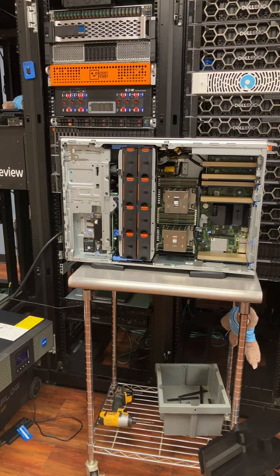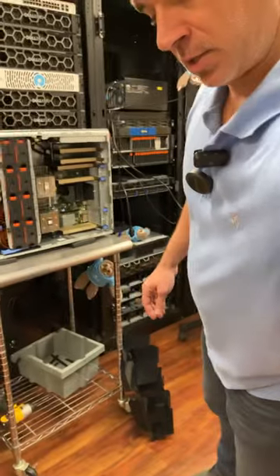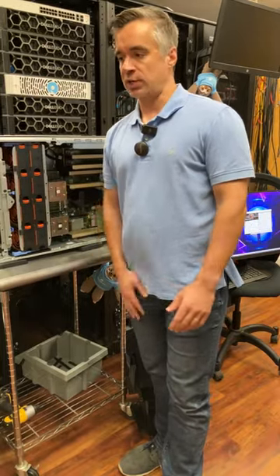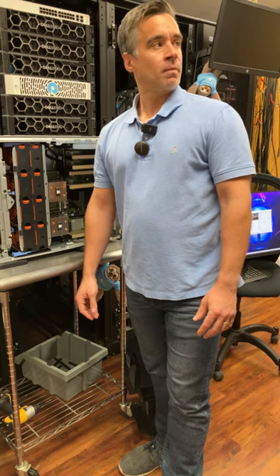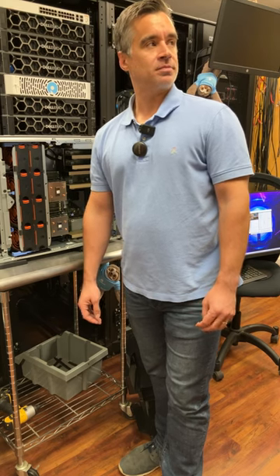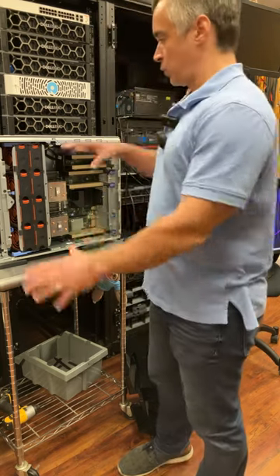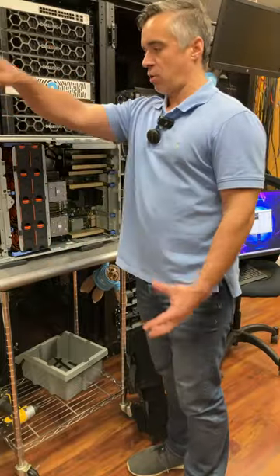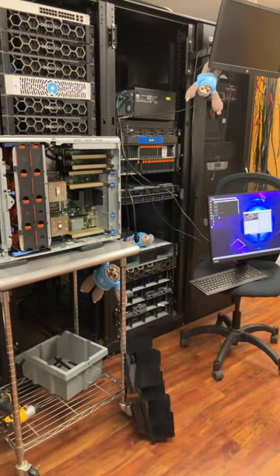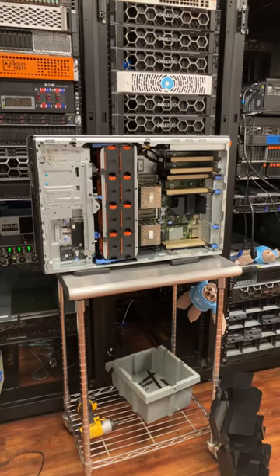I don't know if you were talking about it, but we spent a bunch of time in Dell's labs in Round Rock, and they've got sound booths set up just for the servers and all the workstations and everything else, and their anechoic chambers are completely soundproof. You set up your unit under test with like a billion microphones around it. So it would be this server with a mic array all the way around, and then you can do things like idle, power up, reboot, under load for storage, all sorts of other things as you figure out what the impact is.